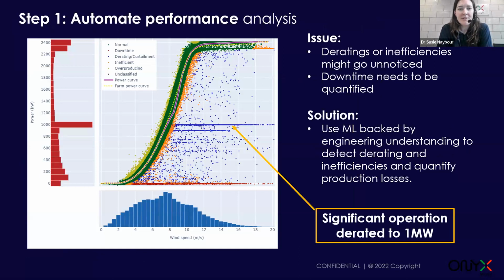On the left, you can see a power curve. The axis along the bottom is the wind speed, and coming up is the power. There's a curve where most points fit, shown as a yellow line for the site and a purple line for this particular turbine. You can see a distribution on the bottom of where the wind is, mostly around 8 meters per second, and the power in another chart. It goes up to 2,400 kilowatts, but there's a big bar at 1,000 kilowatts, which is a derating on this turbine.